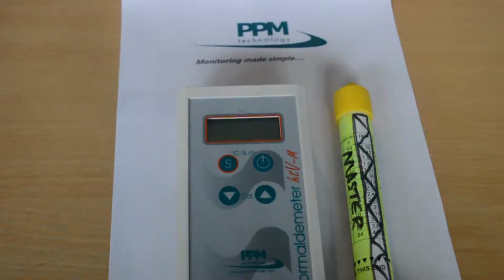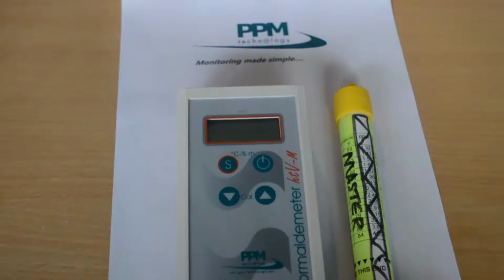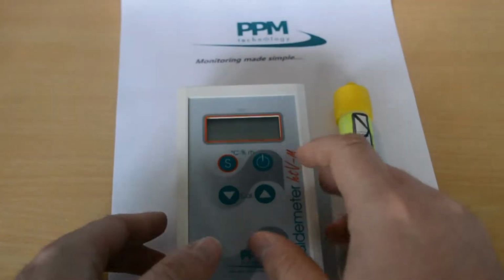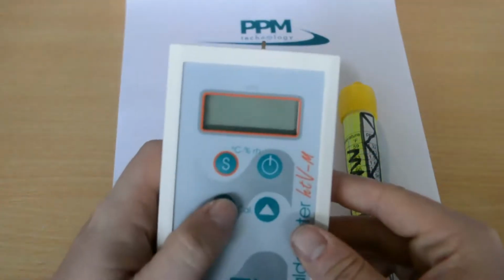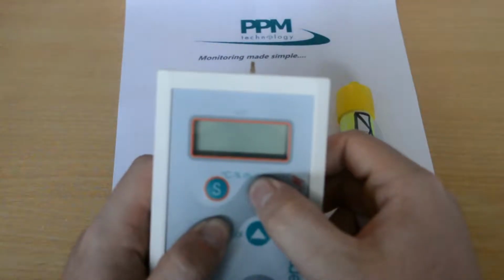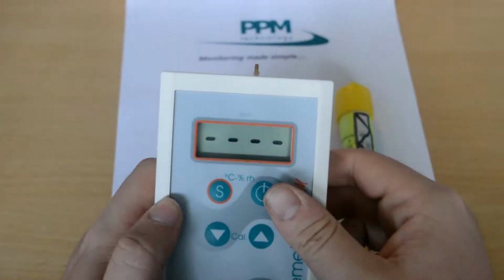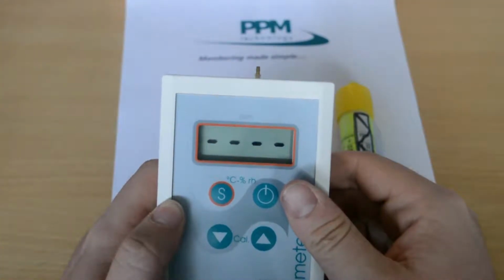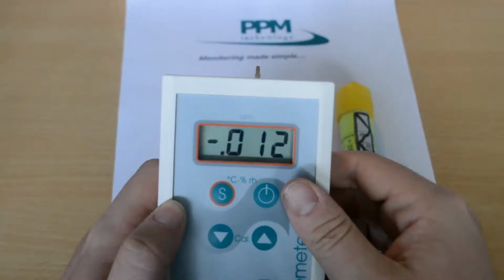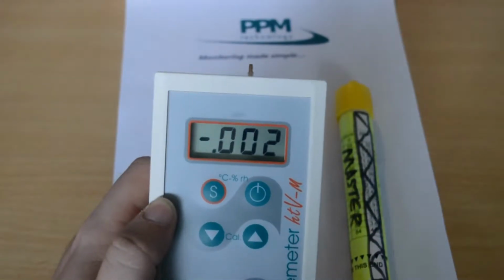Typically, there are three main reasons for the display to flash 4 dashes and the instrument not sampling. These are: the instrument has been accidentally calibrated when no calibration standard was present, or the calibration standard used for the calibration has expired, or the instrument has been damaged and will need to be repaired. To determine which of these reasons apply, carefully follow the procedure as it is outlined.